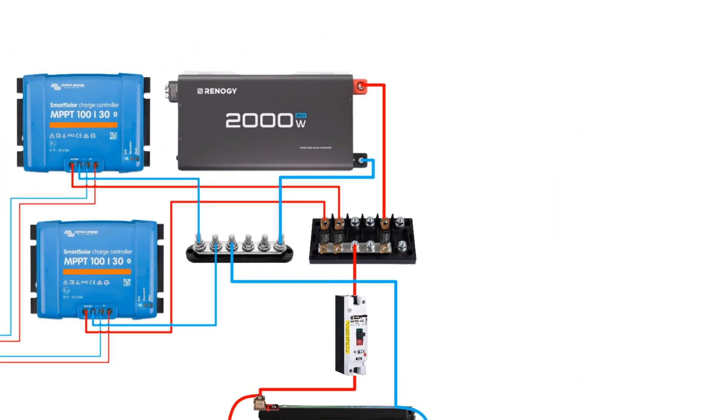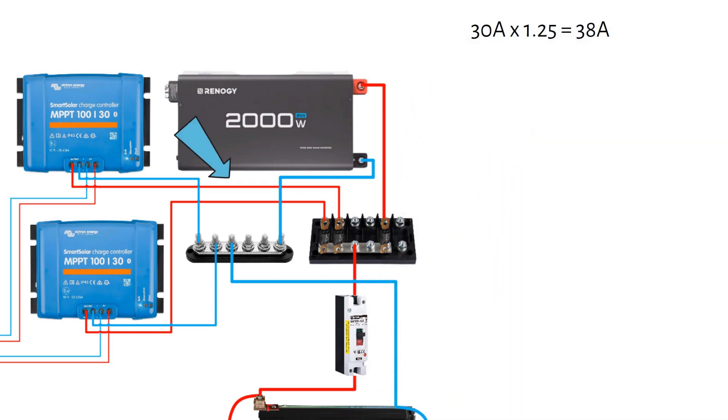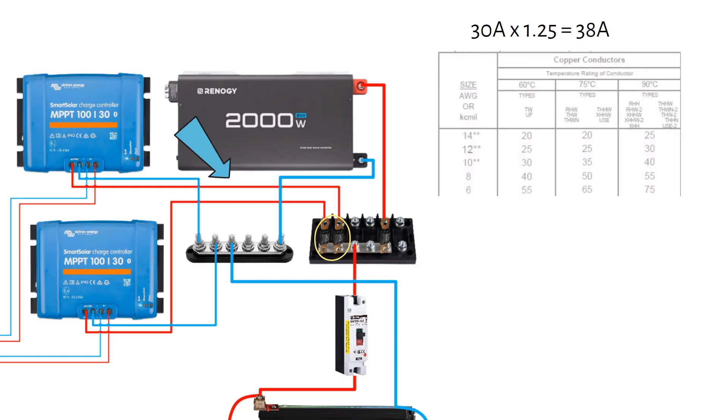From the charge controller to the bus bar the maximum current is 30 amps. With a safety factor that becomes 38 amps. So I use a 40 amp fuse and an 8 gauge or 10mm square cable.